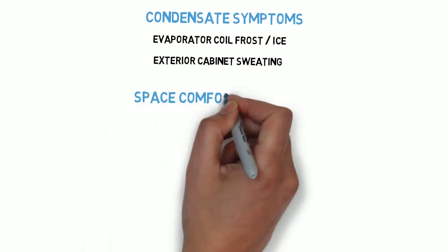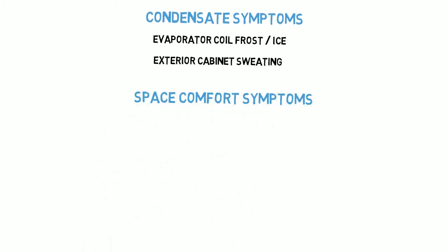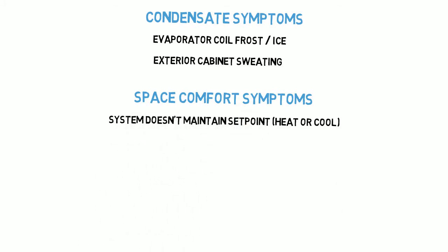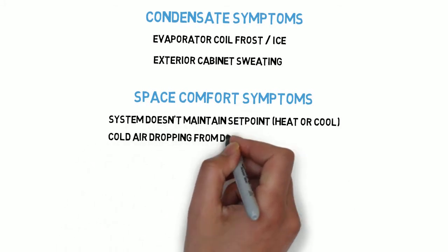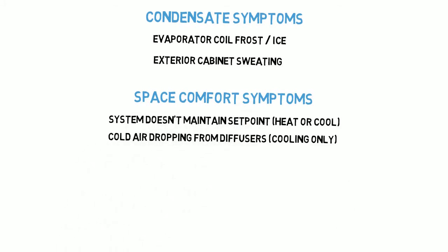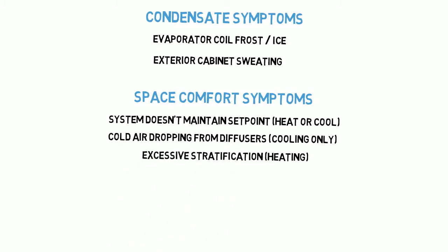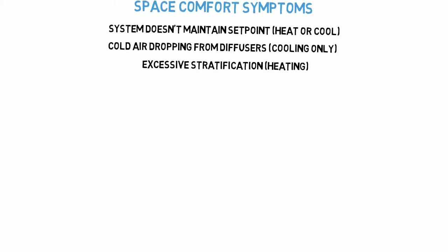Space comfort symptoms of low air flow: doesn't maintain set point, cold air dropping from diffusers with not enough velocity, excessive stratification in heating — the hot air rising up to where the people aren't.